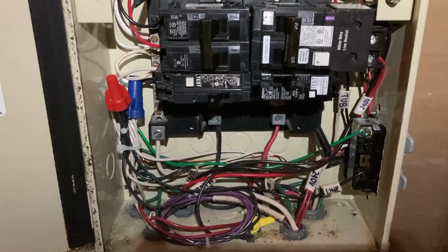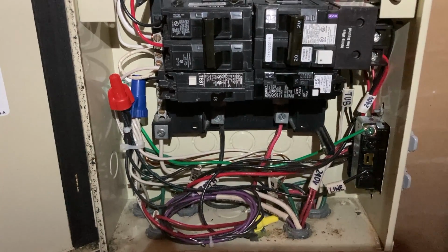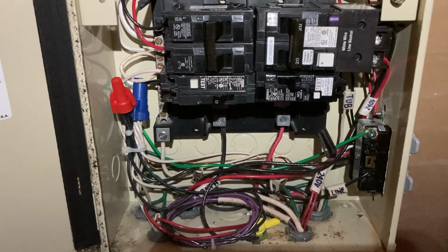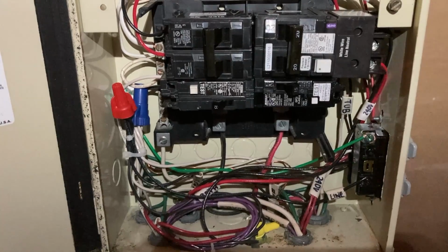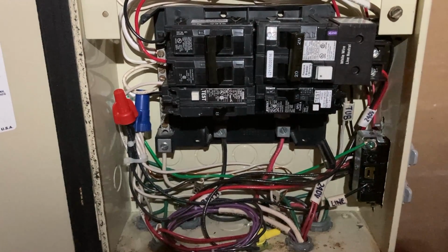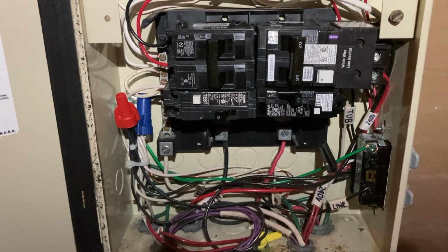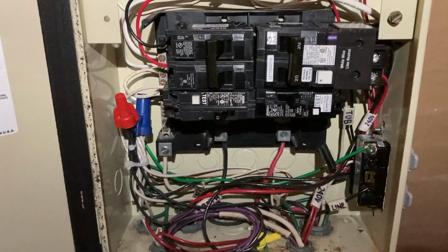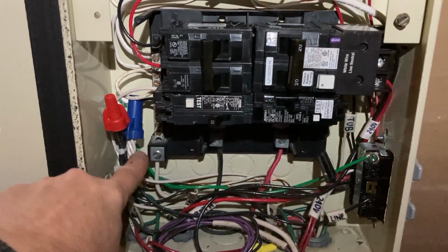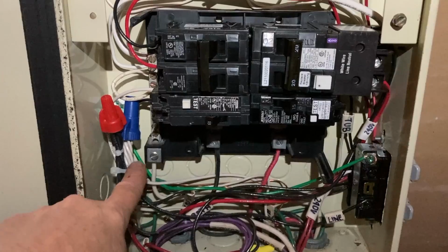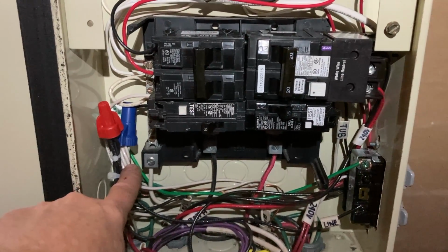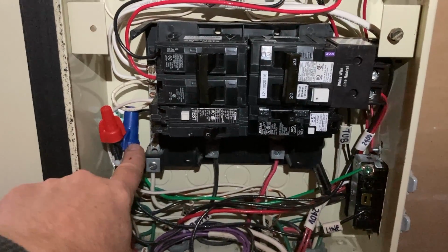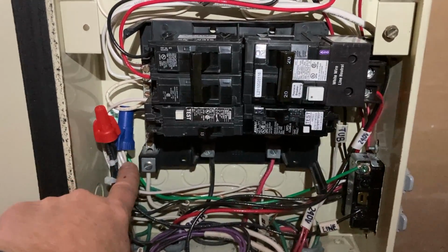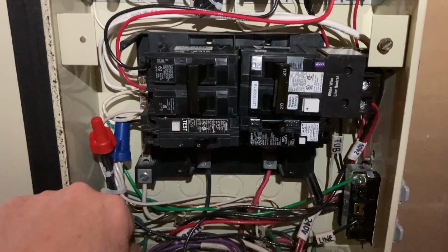So everything's all wired. What do we think? Better or just different? It's hard to get standard wire to lay neatly, but I know electrically it's better because the hot tub's on its own circuit now, and the new pump will be GFCI'd, so that's good. I like having all the neutrals come to one point instead of having them all over the box - these are all the general purpose neutrals. I wound up putting them under a blue wire nut, and I upsized when I actually counted how many I was sticking under there.